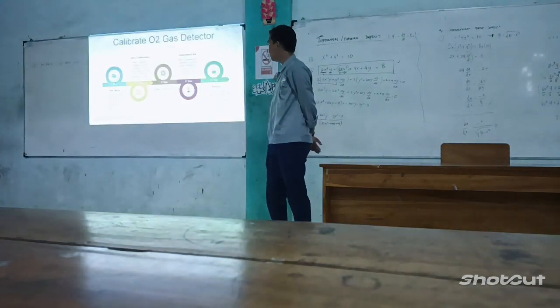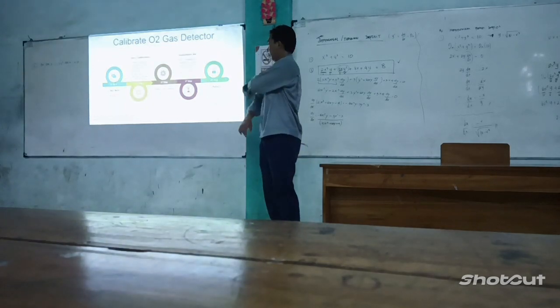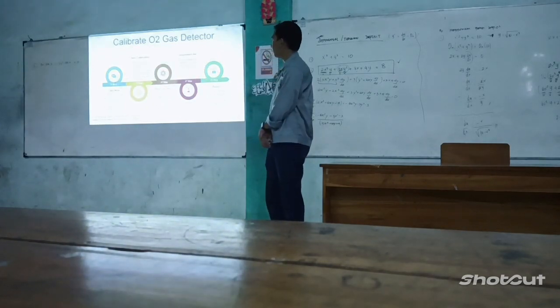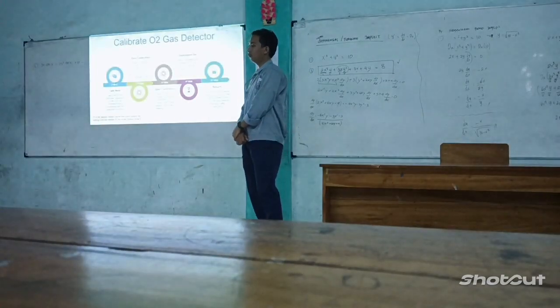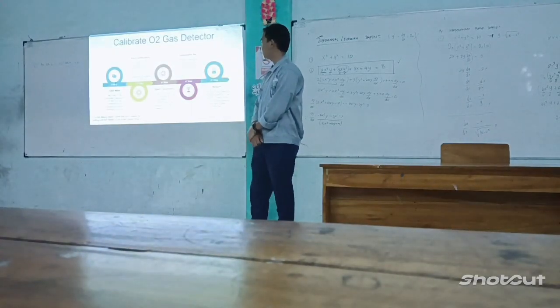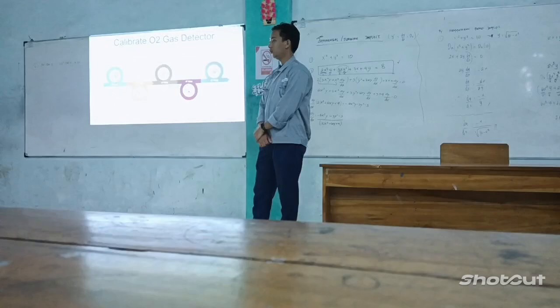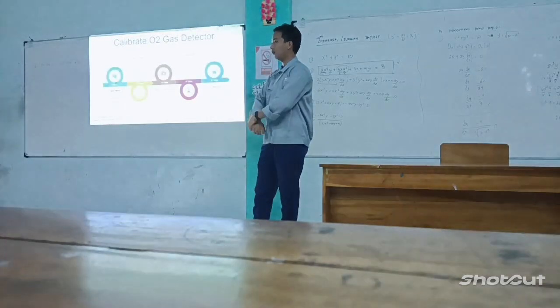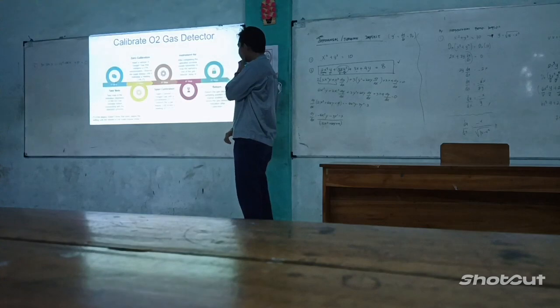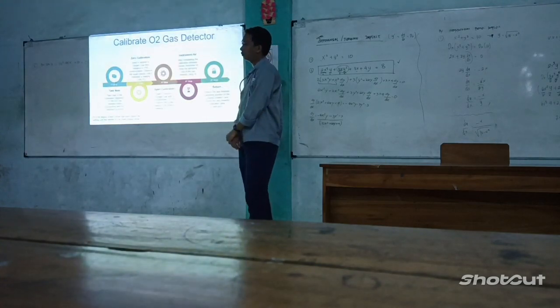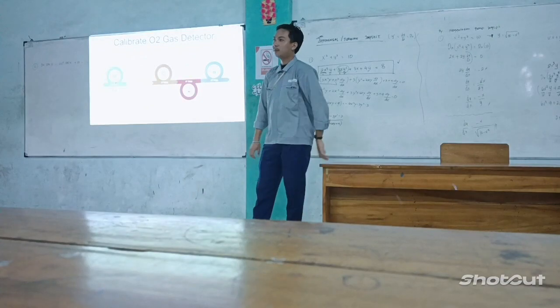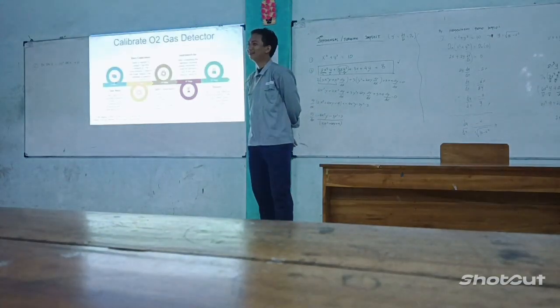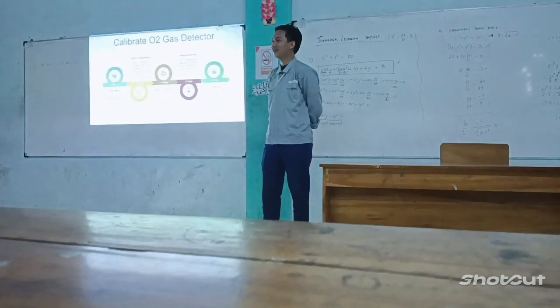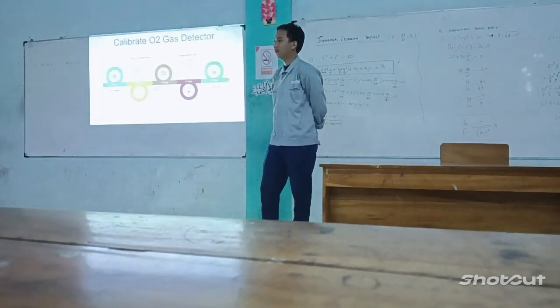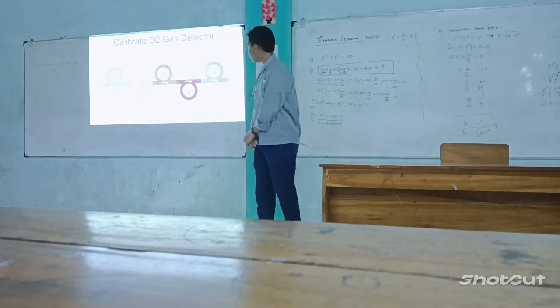I have a question in zero calibration. It says insert a sample of oxygen gas that contains 2.5% concentration. My question is, that section is zero calibration, but why must we see the scale until it indicates a reading of 2.5? Why not zero? Sorry, my English. My question is, the first step is to put the sample or zero in the equipment first.